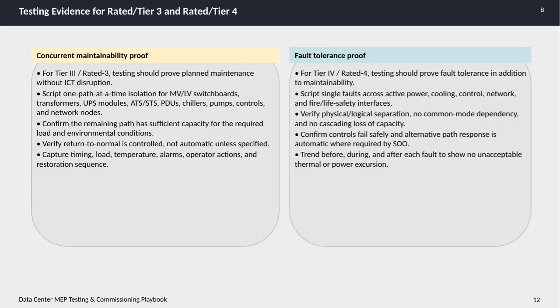Let's talk about the testing evidence required for rated or Tier 3 and Tier 4 data centers, focusing on two key concepts: concurrent maintainability and fault tolerance. Starting with Tier 3 or rated 3, the main goal is to prove concurrent maintainability. This means we need to demonstrate that planned maintenance can be performed without disrupting the information and communication technology systems. The testing approach involves isolating one path at a time in critical components like medium and low voltage switchboards, transformers, UPS modules, ATS and STS systems, power distribution units, chillers, pumps, controls, and network nodes.